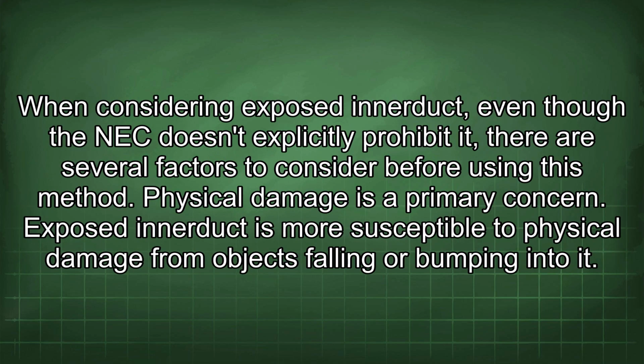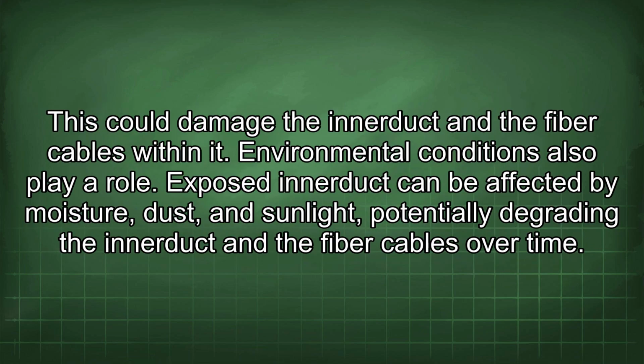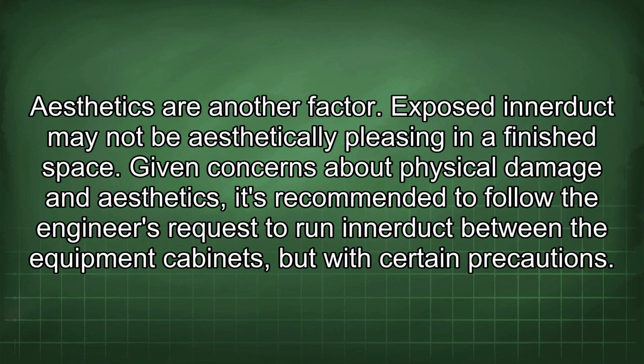When considering exposed Innerduct, even though the NEC doesn't explicitly prohibit it, there are several factors to consider before using this method. Physical damage is of primary concern. Exposed Innerduct is more susceptible to physical damage from objects falling or bumping into it. This could damage the Innerduct and the fiber cables within it. Environmental conditions also play a role. Exposed Innerduct can be affected by moisture, dust, and sunlight, potentially degrading the Innerduct and the fiber cables over time. Aesthetics are another factor. Exposed Innerduct may not be aesthetically pleasing in a finished space.